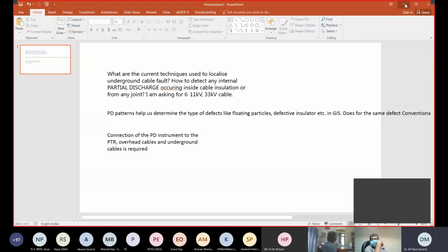Damped AC, DAC. For medium voltage it's allowed, for high voltage not. This is due to the physical reason that the PD activity - this is valid for commissioning tests, not for diagnostics. Because as I said, you need two things: electrical field and charges. If you use it for diagnostics, it's allowed because you already have charges. If you disconnect from the rated voltage and use the damped AC, you can start the PD activity. These are physical reasons I don't want to go into detail on - again, this is described in the technical brochures I've given in the references, the additional ones, where you'll find the physical explanations. It's not so easy to describe in words.